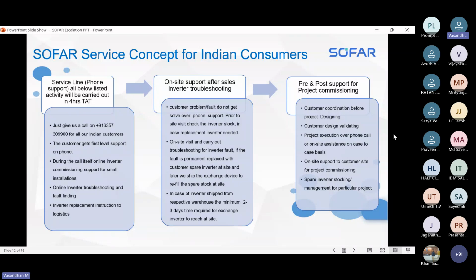For pre-commissioning and post-commissioning, I'll mention one thing: for projects above 100 kilowatt, we need to use a pre-commissioning project report. Every distributor and dealer should share this with customers installing above 100 kilowatt inverters. They have to fill the pre-commissioning report and get clearance from our SOFAR engineer by mail. Only then can commissioning above 100 kilowatt be allowed.